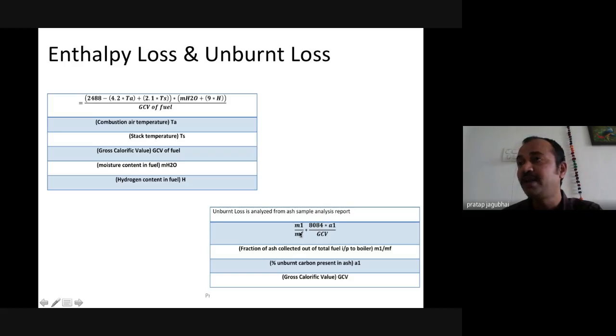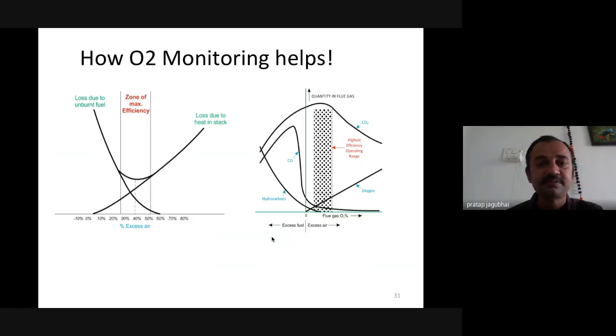But the unburnt loss can be controlled by providing sufficient excess air, not higher excess air, not less air, but sufficient excess air such that there should be no black smoke from the chimney, and the ash collected from the furnace or from the heat recovery equipment should not have carbon content.